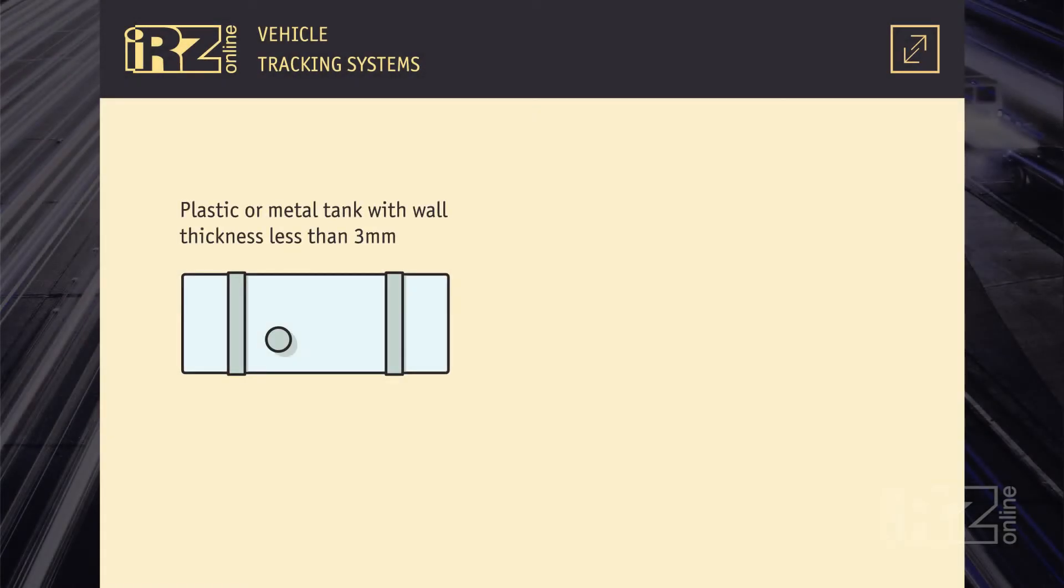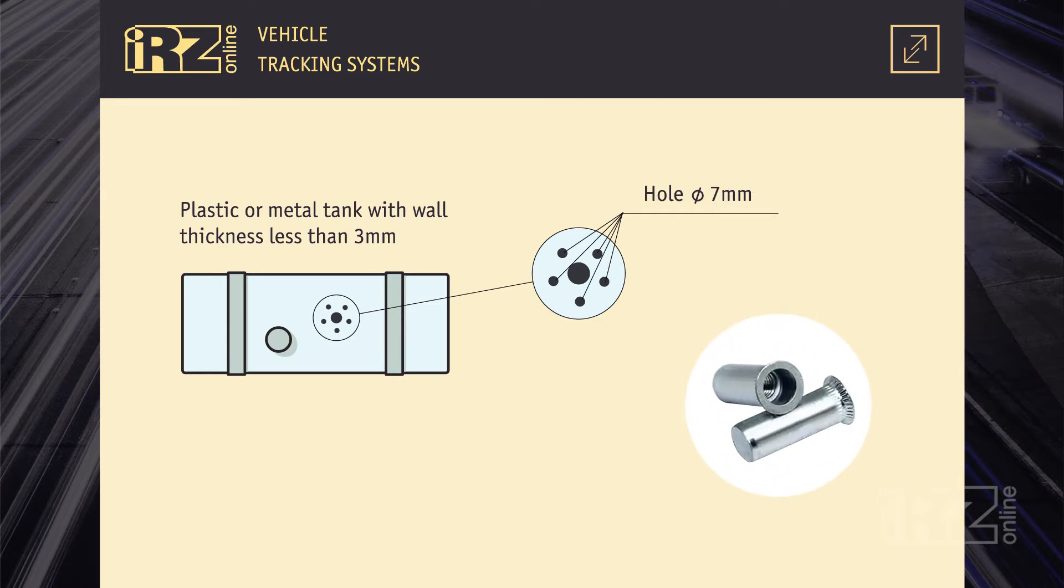For a metal tank with a thickness less than 3 mm or for a plastic tank, make the hole diameter of 7 mm and use the stack bolts supplied with the sensor. In our case, we use the stack bolts.